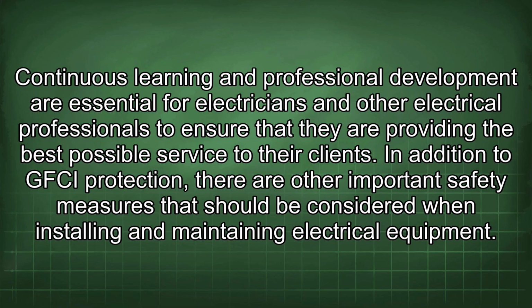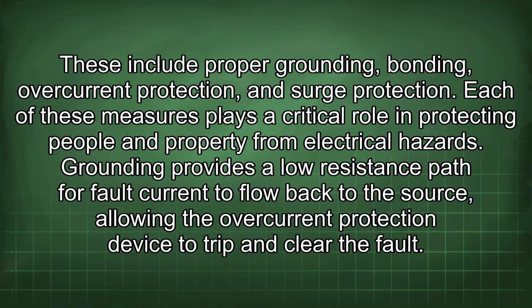In addition to GFCI protection, there are other important safety measures that should be considered when installing and maintaining electrical equipment. These include proper grounding, bonding, overcurrent protection, and surge protection. Each of these measures plays a critical role in protecting people and property from electrical hazards. Grounding provides a low-resistance path for fault current to flow back to the source, allowing the overcurrent protection device to trip and clear the fault.